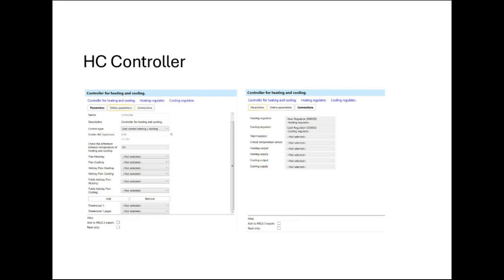So you can use all our actuators, all our thermostats to work in this ecosystem. So this is the basic way of controlling fan coils and also the normal heating systems in Europe, and FCUs mainly in the Middle Eastern region for cooling. You can achieve energy management through this virtual heat cool controller because you have an option to connect a window detector. So when the window detector is open, you can turn off the heat cool controller. Also, you can club a motion detector. So when there is no motion, you can turn off the heat cool controller. This is how you can achieve energy efficiency in this virtual controller.